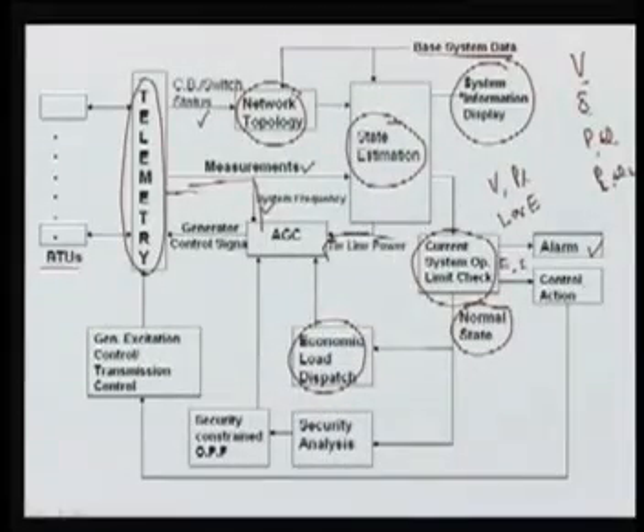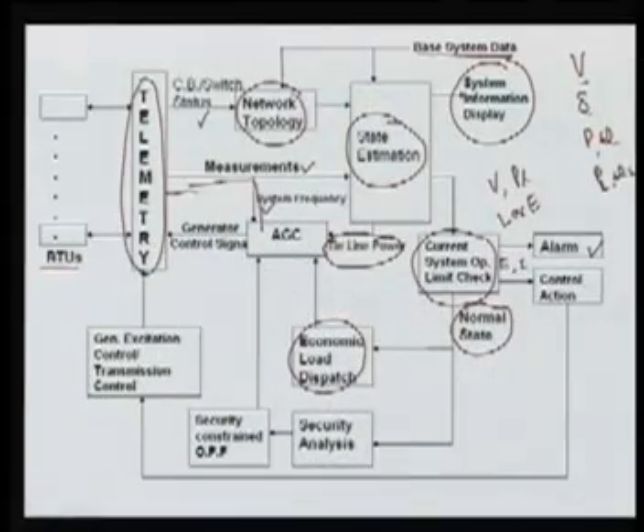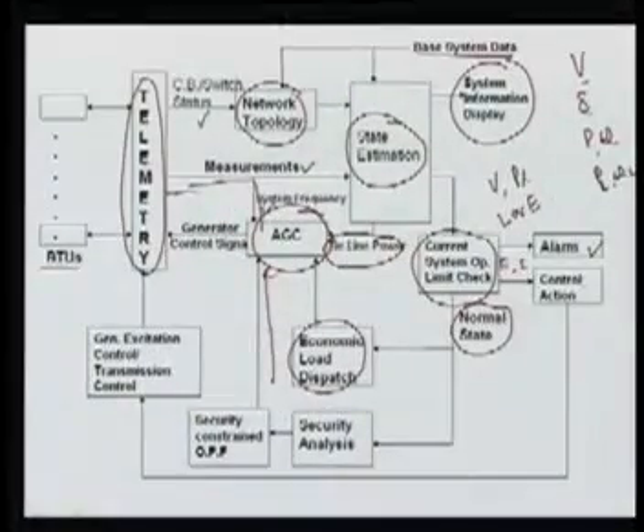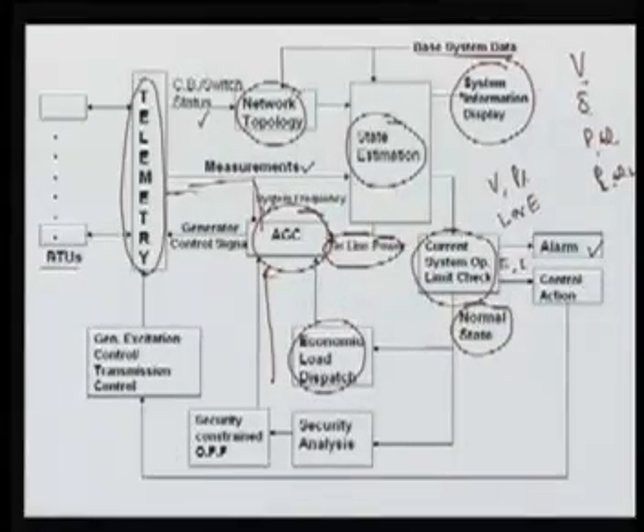So we require the tie line power flow, the present settings of the generators, and also the security constraints with the OPF. Then finally we solve the automatic generation control. This automatic generation control will give some signal to the generators. It again goes through the telemetry communication, because this whole process is not necessarily sitting at the generating station. It may be somewhere else, normally in the state load dispatch centers. The generator settings will pass to the various generators, and then we can give this signal and achieve our desired outputs.